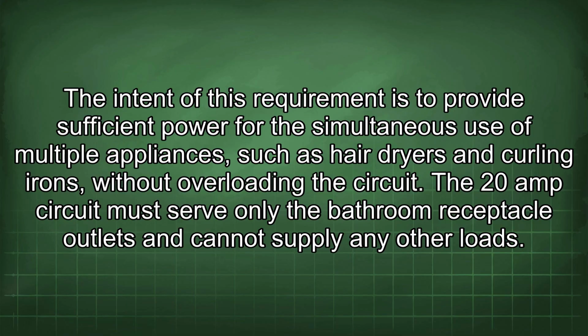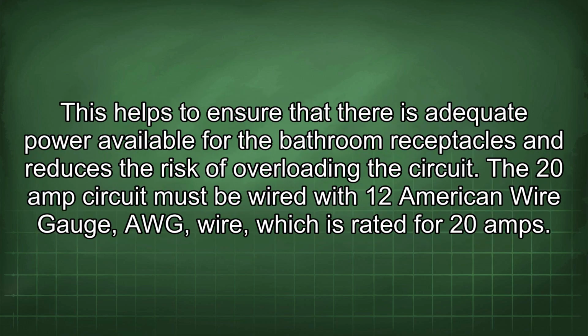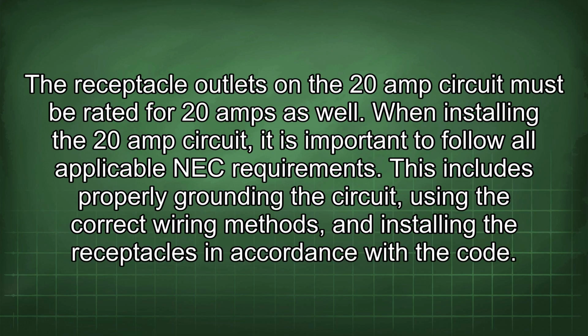A 20-amp circuit must serve only the bathroom receptacle outlets and cannot supply any other loads. This helps to ensure that there is adequate power available for the bathroom receptacles and reduces the risk of overloading the circuit. The 20-amp circuit must be wired with 12 American wire gauge (AWG) wire, which is rated for 20 amps. The receptacle outlets in the 20-amp circuit must be rated for 20 amps as well.